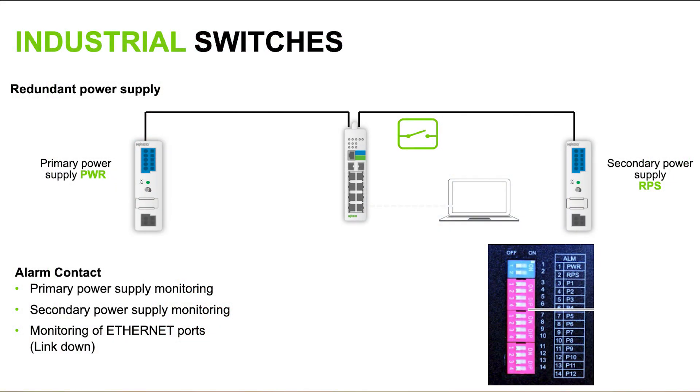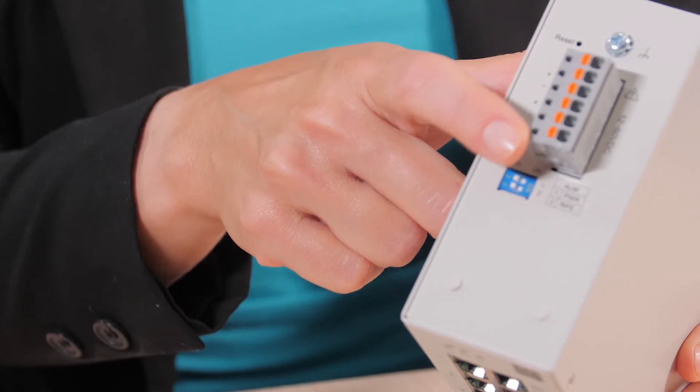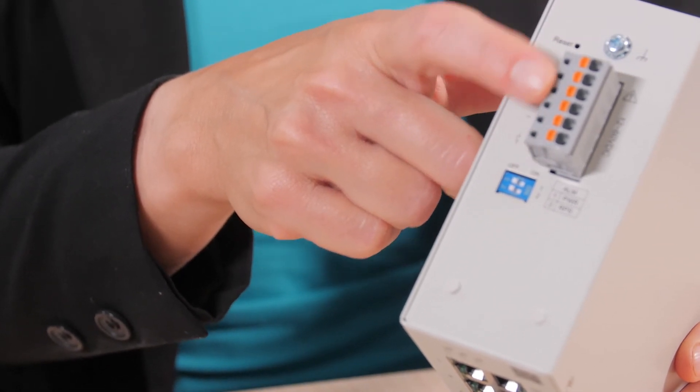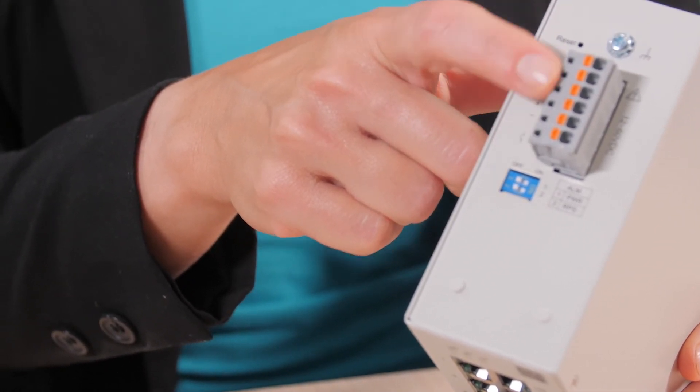WAGO lean managed switches also accept two different power supplies, a primary and a secondary, and can trigger alarm relays if one should fail. The alarms are set through DIP switches located near the power connections. Ethernet switches can keep operating should one power supply fail, but it will let a plant operator know of the issue.